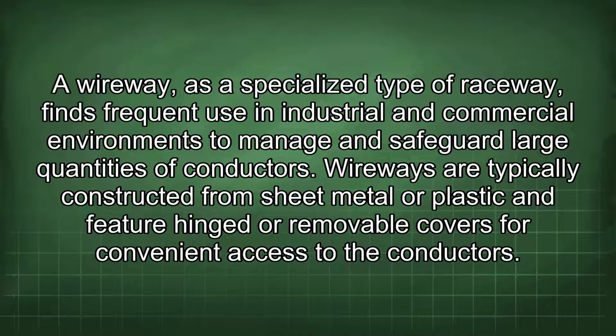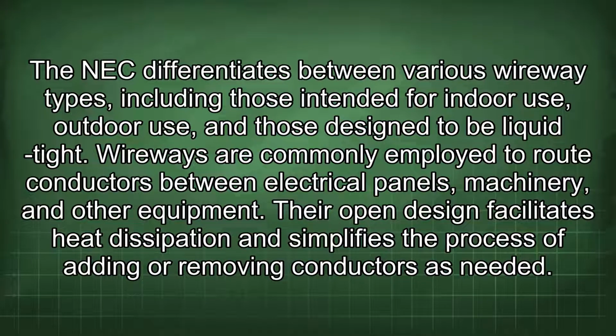A wireway, as a specialized type of raceway, finds frequent use in industrial and commercial environments to manage and safeguard large quantities of conductors. Wireways are typically constructed from sheet metal or plastic and feature hinged or removable covers for convenient access to the conductors. The NEC differentiates between various wireway types, including those intended for indoor use, outdoor use, and those designed to be liquid-tight. Wireways are commonly employed to route conductors between electrical panels, machinery, and other equipment. Their open design facilitates heat dissipation and simplifies the process of adding or removing conductors as needed.